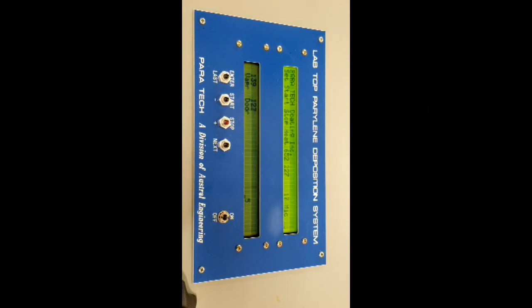Okay, we'll come back later, and once the vaporizer and the door cool down a little bit, they generally recommend it to be at least below 100 C before you open it up. We'll open up the vaporizer door, and we'll take a look at the fixturing that we have here in the cold probe. And I'll go ahead and shut the fixturing motion off, as well as the cold probe, by using our circuit breakers here on the left hand side next to the main power.